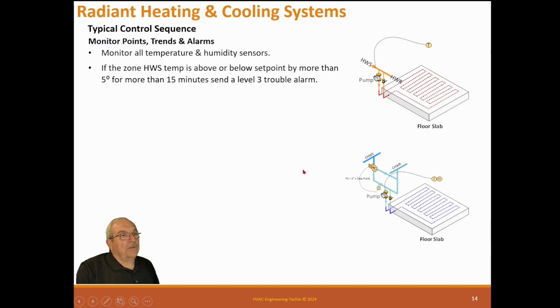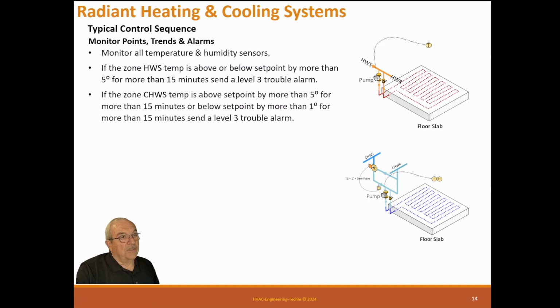Monitor points, monitor all temperature and humidity sensors. If the zone hot water supply temperature is above or below set point by more than 5 degrees for 15 minutes, it's a level 3 trouble alarm. If the chill water supply temperature is above or below set point by 5 degrees for more than 15 minutes, or below set point by more than 1 degree, it's a level 3 trouble alarm.